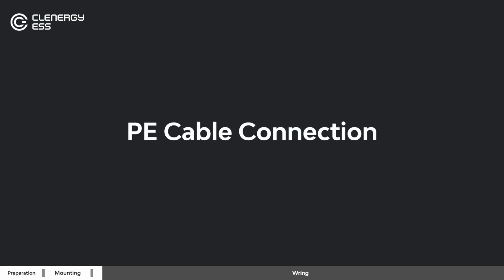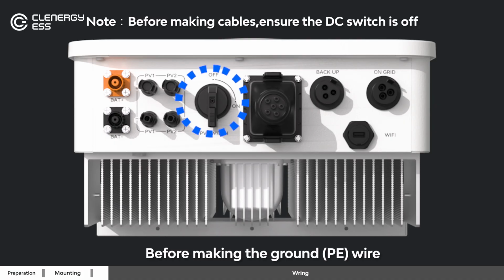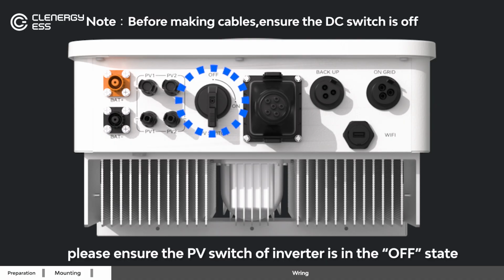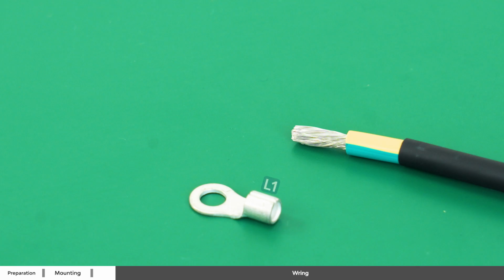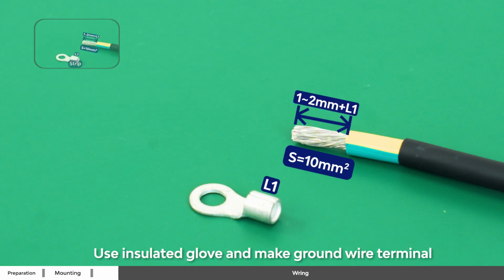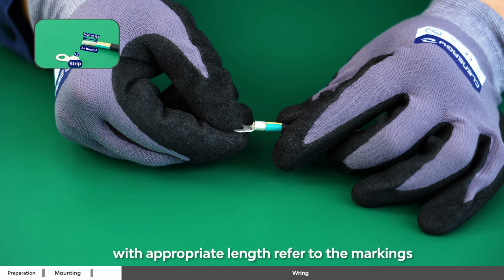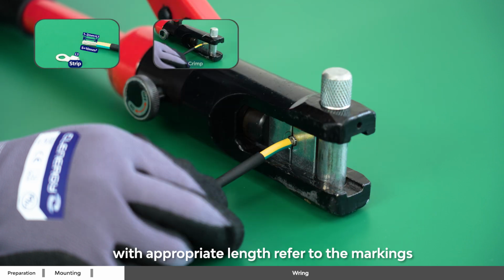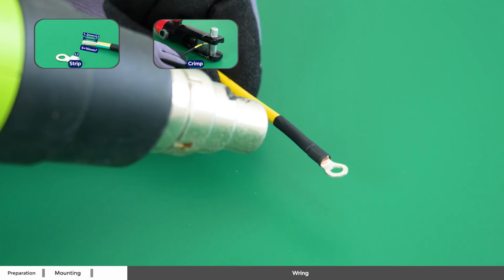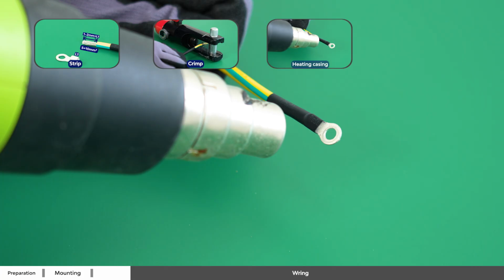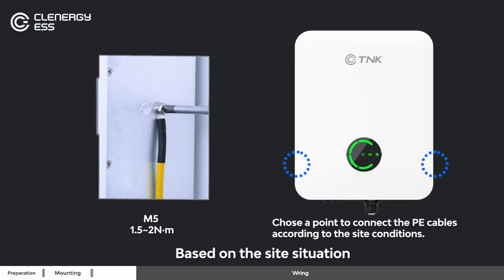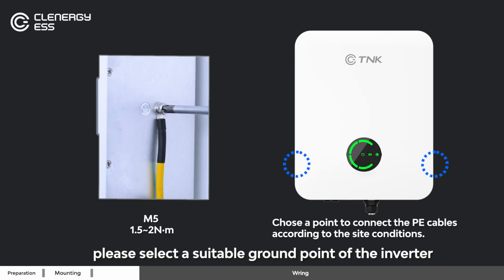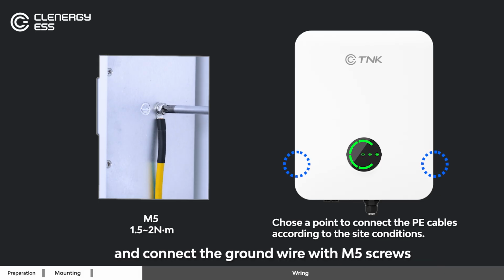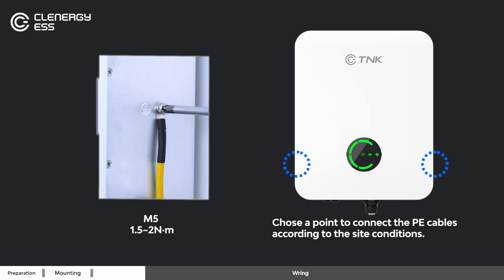PE cable connection. Before making the ground wire, please ensure the PV switch of inverter is in the off state. Use insulated gloves and make the ground wire terminal with appropriate length. Refer to the markings. Based on the site situation, please select a suitable ground point of the inverter and connect the ground wire with M5 screws.